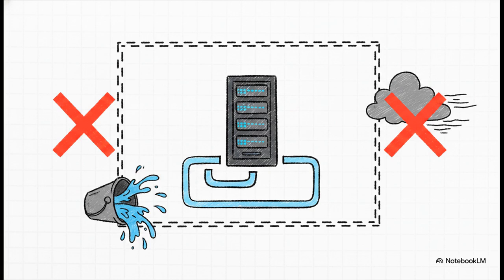No way. Many air-cooled data centers still use a closed loop of chilled water entirely inside the building. It's just that the heat is eventually pushed to the outdoor air. And conversely, many water-cooled data centers still cool the actual server room using indoor air handling units. The water part mainly refers to the central plant transporting and rejecting that heat out via the cooling towers.